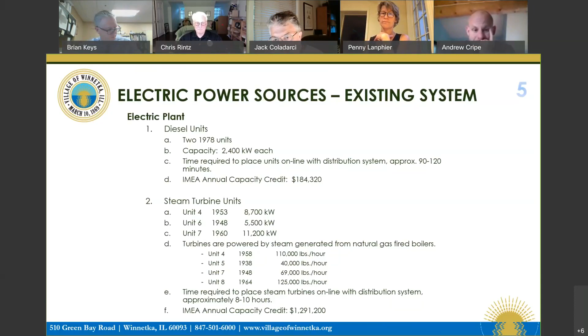On the steam turbines, there are three steam turbines, and the steam is generated from four natural gas-fired boilers, previously fed from coal but now converted to natural gas. Coming up from a cold start, it takes basically 8 to 10 hours to get all steam turbines to maximum output. Annual capacity credits for the steam turbines are 1.29 million. For those who didn't have the opportunity to sit through the recent rate study, it had some enlightening data points. Everybody was ready to throw me off the podium. The 2017 rate study did affirm, based on the current finances of the electric plant, that it provides a significant financial benefit in keeping our wholesale power costs under control. But there is also the reality that, given the age of that equipment, a good run will come to an end at some point in the future.